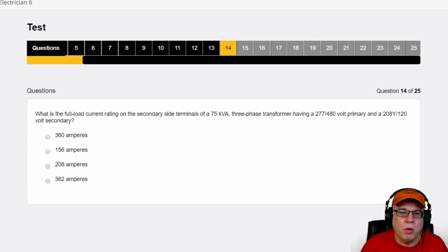So what do we have here? First, we know it's 75 kVA. Remember that tip I always tell you - I always convert this into VA, the total amount. So the first thing I do is 75, and K equals 1,000, so it's 75,000 VA. I write that down first. That's the first thing I do.